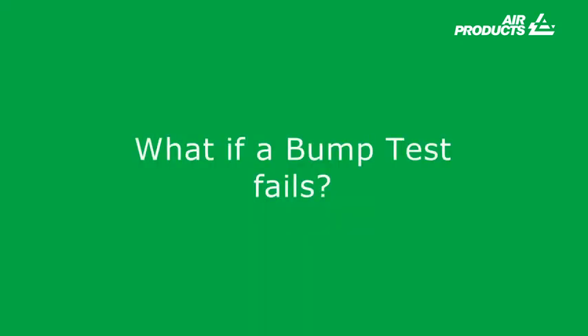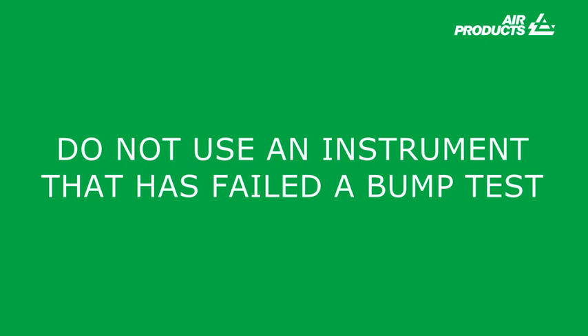What if a bump test fails? Most docking stations will notify the user that an instrument has failed a bump test. Manually bump tested instruments will not indicate if a bump test has failed. Therefore, documented procedures must be adhered to. Do not use an instrument that has failed a bump test. How do you know if a bump test has passed or failed? Typically, an instrument will display a bump test failure warning. This warning will differ from manufacturer to manufacturer. Most docking stations record all tests, passes and failures and include certificate generation software.